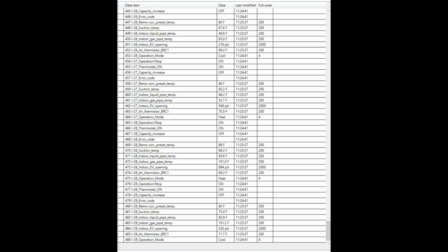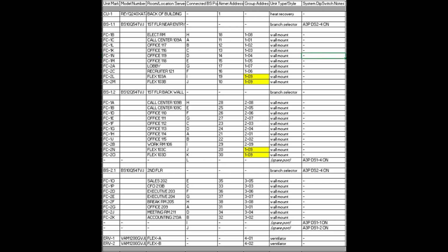All we know with certainty at this point is that port B, which is group address 1-02, actually got landed on what we think is port C, I-29, group address 1-03. We know this because from our as-built sheets, it says 1-02 was originally installed and wired to port B, while group address 1-03 was landed on port C. There is, of course, a possibility that our as-builts are wrong, so we want to assume nothing yet.